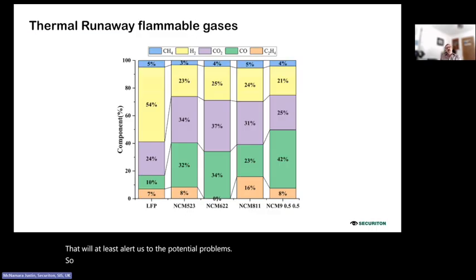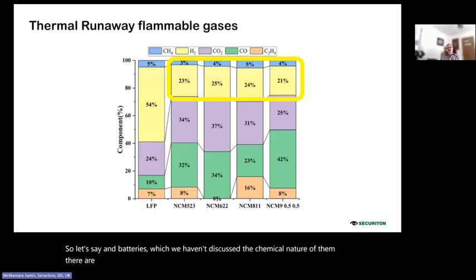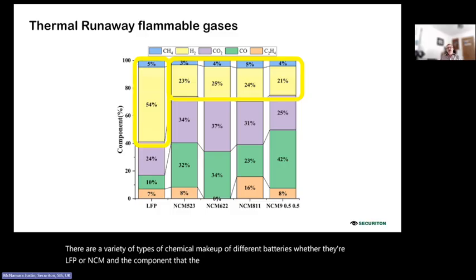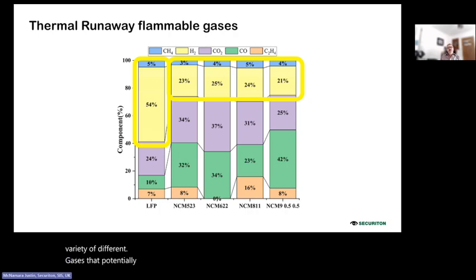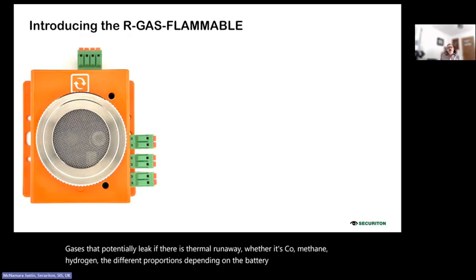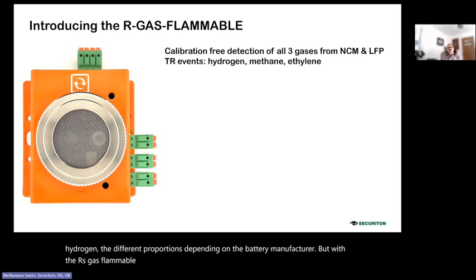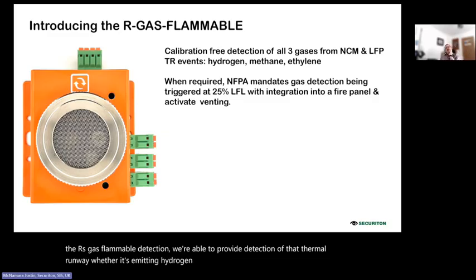So let's say, and batteries, which we haven't discussed the chemical nature of them, there are a variety of types of chemical makeup of different batteries, whether they're LFP or NCM, and the chemical component parts of those, it's a variety of different gases that potentially leak if there is thermal runaway, whether it's CO, methane, hydrogen. They're different proportions depending on the battery manufacturer. But with the R-gas flammable detection, we're able to provide detection of that thermal runaway, whether it's emitting hydrogen, methane, ethylene. We can detect it using this R-gas flammable sensor.